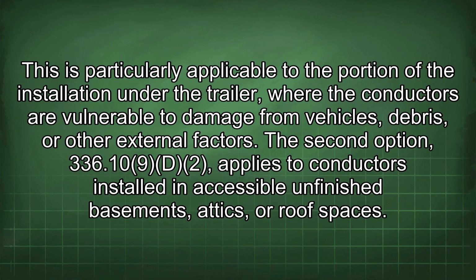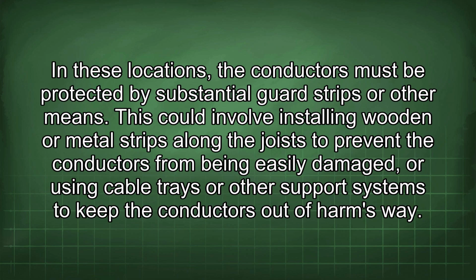The second option, 336.109 D2, applies to conductors installed in accessible unfinished basements, attics, or roof spaces. In these locations, the conductors must be protected by substantial guard strips or other means. This could involve installing wooden or metal strips along the joists to prevent the conductors from being easily damaged, or using cable trays or other support systems to keep the conductors out of harm's way.